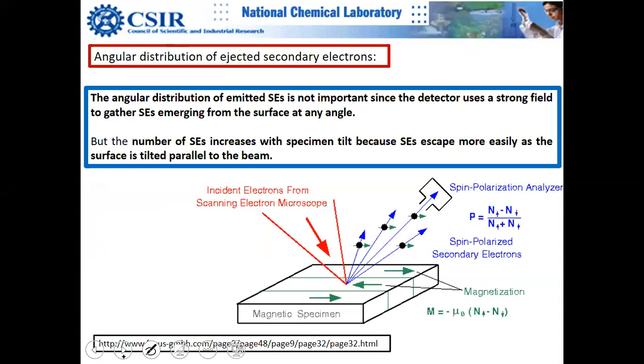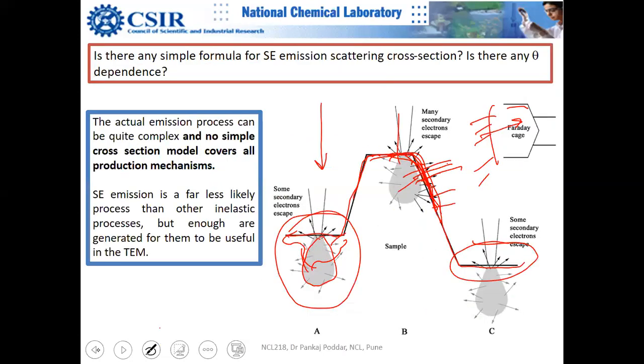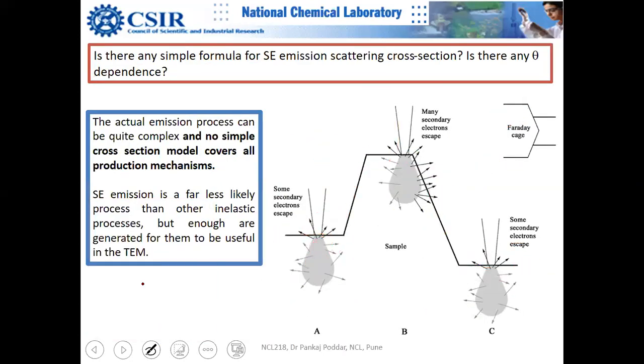The angular distribution of secondary electrons is not critically important because a positive bias voltage is applied at the detector to attract them. Even if an electron is ejected in an oblique direction, it will curve and reach the detector due to this positive voltage.